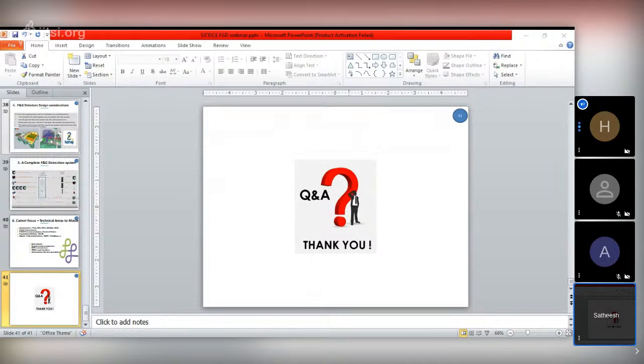You have another question. It is given as transmitter equals sensor plus electronic module, but detector equals what? Actually, what I showed there is transmitter plus sensor equals detector. The gas detector is an instrument consisting of a sensor, which is the basic item to detect the gas, plus the transmitter to give the signal, because the sensor cannot give the signal directly. It is small, like a canister or a lamp. We need additional electronics to amplify the signal and handle all the diagnostics to send it back to the control room.